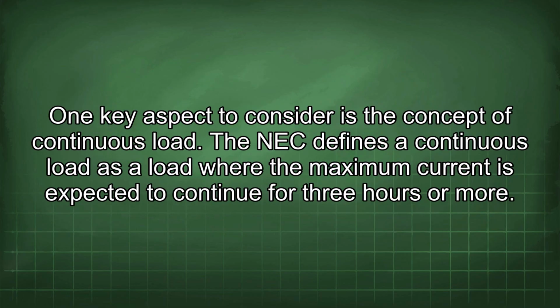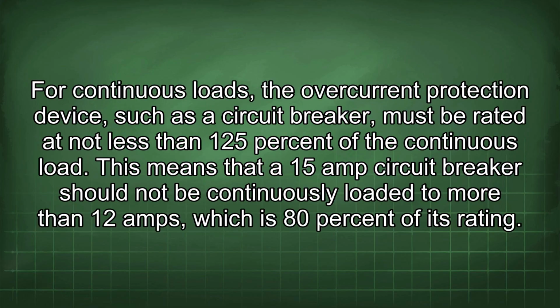One key aspect to consider is the concept of continuous load. The NEC defines a continuous load as a load where the maximum current is expected to continue for 3 hours or more. For continuous loads, the overcurrent protection device, such as a circuit breaker, must be rated at not less than 125% of the continuous load.